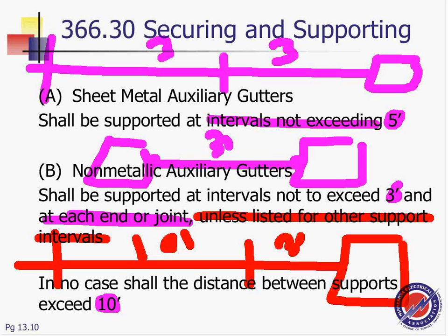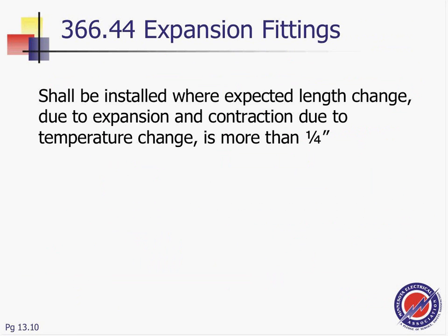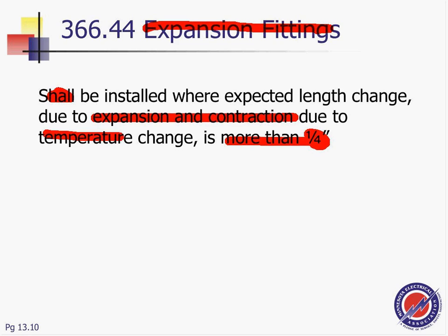So that's a few things about the gutters, guys. Expansion fittings, you have to provide expansion fittings for the non-metallic. If the change in length from expansion or contraction because of temperature is more than a quarter inch, it will shrink or expand more than a quarter inch, then you have to provide an expansion fitting. Expansion fittings shall be installed where the expected length is going to change a quarter inch, like any other conduit.